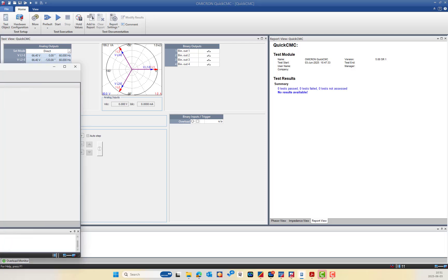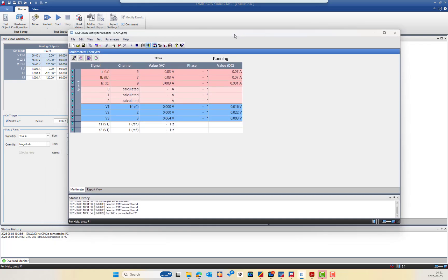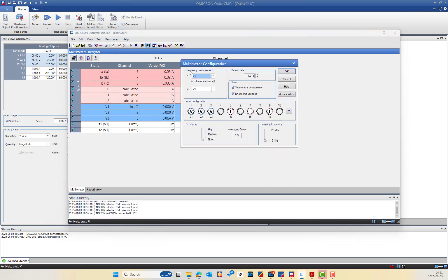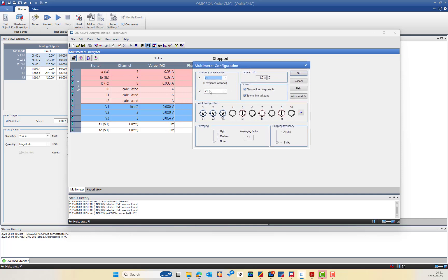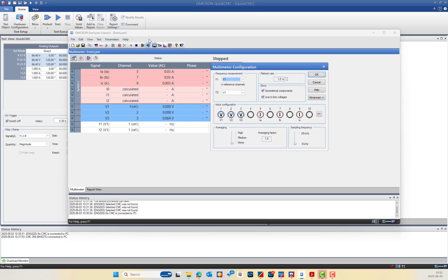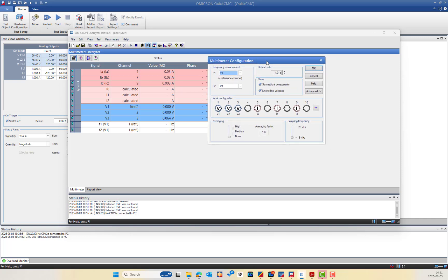Now I will show you the settings of the EnerLyzer Classic module. In the multimeter configuration, the reference channel is set to V1, which is the voltage for phase A. The same reference is used for frequency F2. This enables phase angle measurement for all voltage and current phases, and also measures the nominal frequency, which should be 50 Hz.